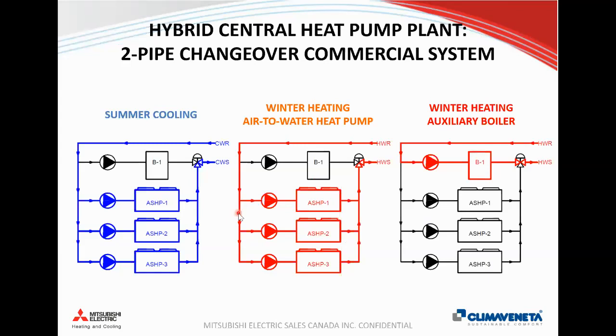Generally speaking, with two pipe changeover systems, you'll select the number of units that you need to meet your cooling or heating capacity. Because you'll need an auxiliary boiler in most applications, I'd recommend that you size these based off the cooling capacity, and then supplement the rest with an auxiliary boiler, either when it's too cold for the heat pumps to run, or depending on the total capacity available from the heat pumps, with a backup boiler. You could add more heat pumps to meet more of the heating load in winter if you wanted to. It really just comes down to capital cost. If you only need to run 3 units in summer for cooling, but you need 5 units for heating in winter, is the building owner going to buy an extra 2 units just to meet a little bit more capacity in winter?